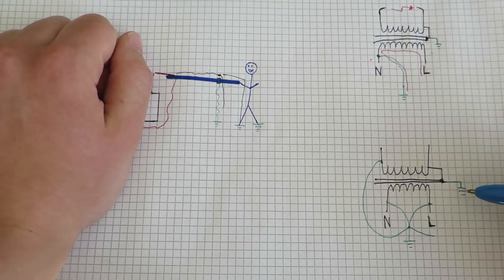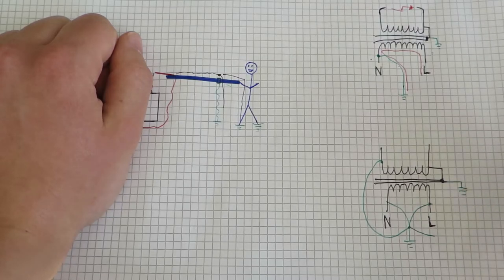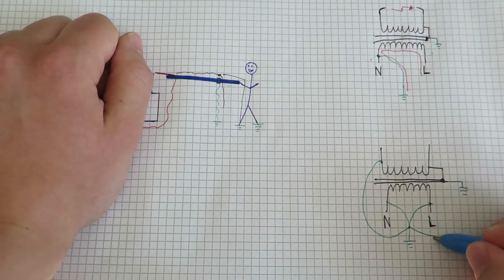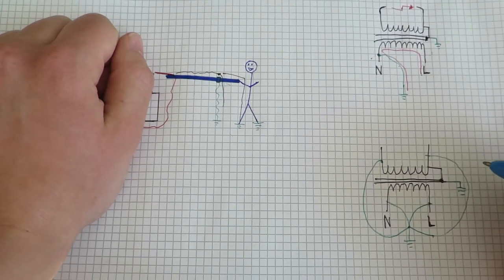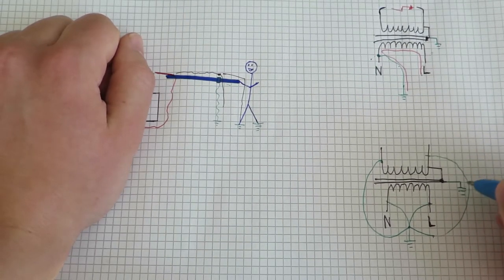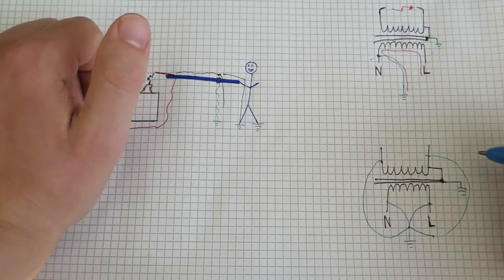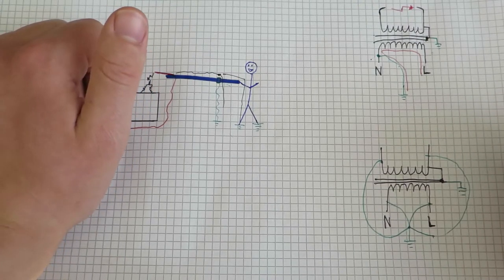Here you theoretically just need one clip because one end of the transformer is usually ground. But if your transformer is not grounded, then it is also necessary to use another clip to short out the other side. But if it's grounded, this clip is theoretically not necessary. I still use it in case something goes horribly wrong.